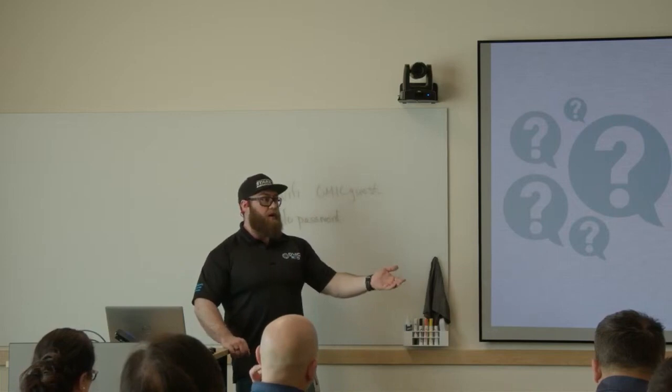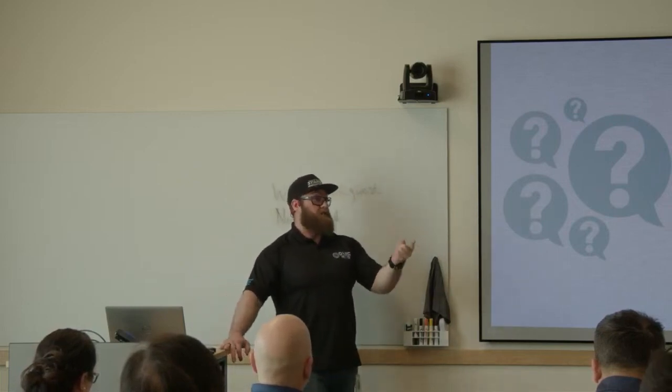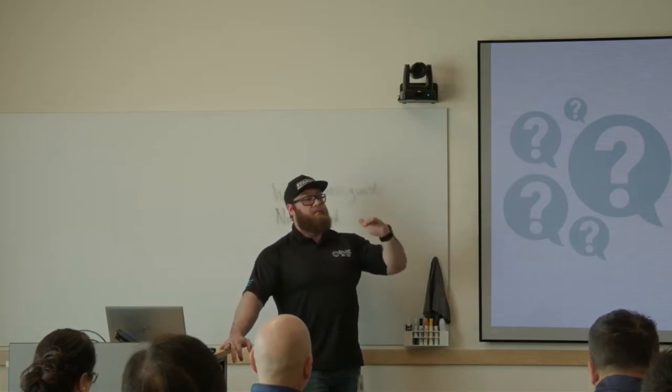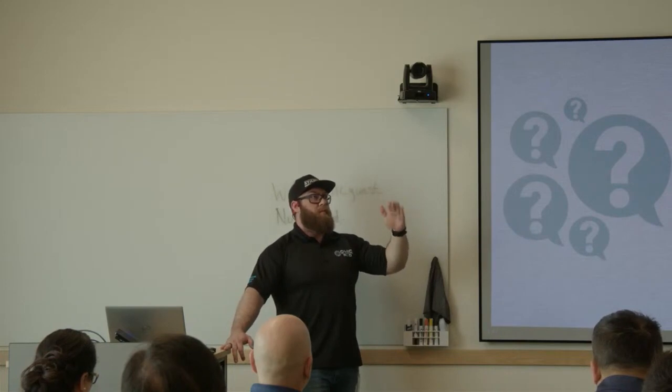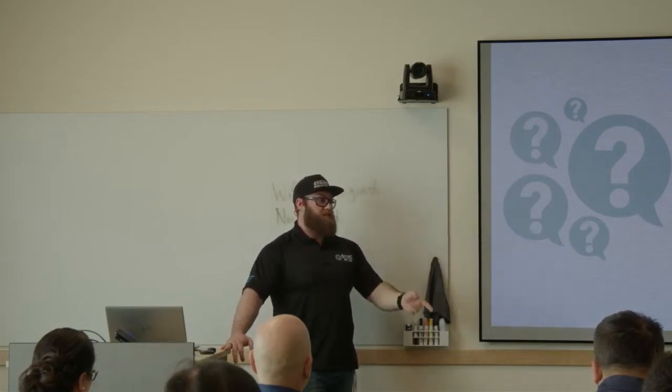That being said, there's just an installation menu where you say what the orientation of your robot is, and they even have pre-existing templates. I think two of the most common templates are the inverse or a 45 degree offset. Once you say that, it'll update the coordinate systems, but more importantly, it'll update the robot on what it thinks its gravity should be when the brakes are released.